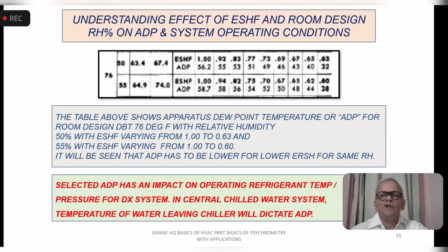So if you have the chilled water temperature set already and you get some spaces having a lower sensible heat factor, demanding a lower ADP to be maintained, then you will have to be extra careful in the selection of the coil. You have to make sure that you are able to achieve that performance. Otherwise, you will not be able to achieve that kind of relative humidity because you will not have that capacity of moisture removal.